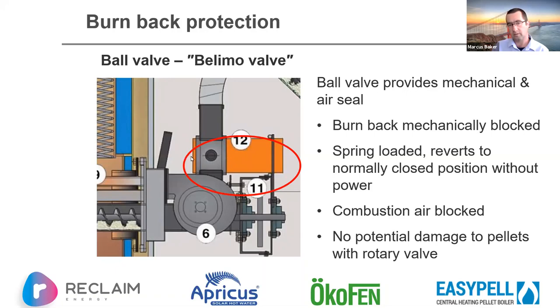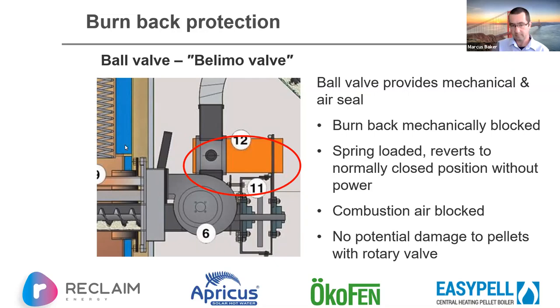With Ökofen it's a ball valve with a normally-closed spring-loaded motor. When the boiler wants fuel it activates the motor, drawing the ball valve open so pellets drop into the auger system, then it closes.